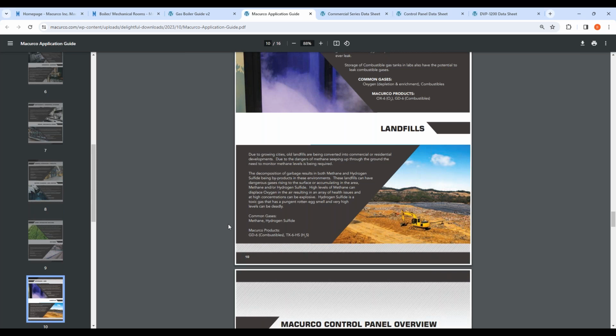We are coming out with several different options here in the next couple months. It's in the process right now, where combustible gas detection - if you're in a mall, an apartment complex, pharmaceutical facility, doesn't matter - they have to have combustible gas detection. So anytime you're dealing with landfills, no matter what state you're in, that's a big one, because we're not talking about just life safety at that point, we're talking about infrastructure safety as well. So a loss of life plus a loss of the business itself - that's pretty much what we're seeing across the board with the methane and the landfills.